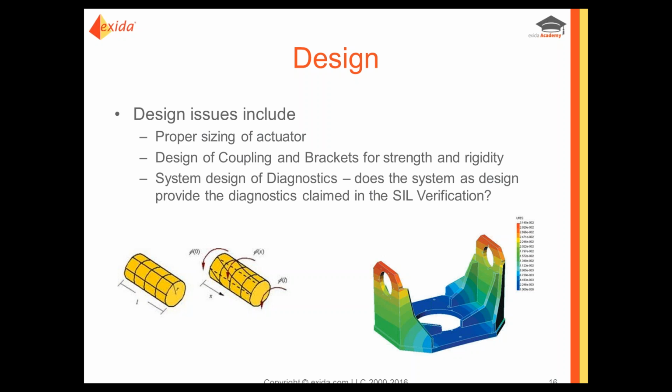You would include that, and then the position switches would be an annunciation failure, so that failure rate would be treated as an annunciation failure or a diagnostic failure within Exsilentia. So by selecting partial stroke testing, you can either manually enter what failures are recategorized as dangerous detected, or you can use some recommended values that Exsilentia would give you. Thank you, those are good questions.